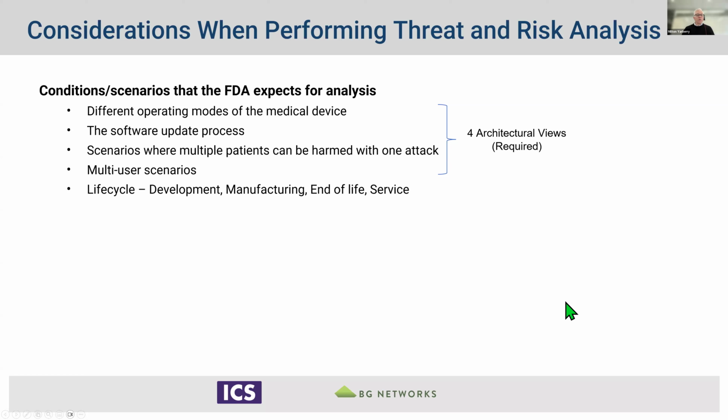And so the next thing I want to take a look at is the considerations you should have in mind when doing the threat modeling and the risk analysis. The conditions that the FDA is expecting you to consider are things like different operating modes of the medical device. By operating modes, that can be, for example, as the device is booting up, or if the device is in an error state. You're expected to look at security in those modes because in those gaps, exploits can be found.